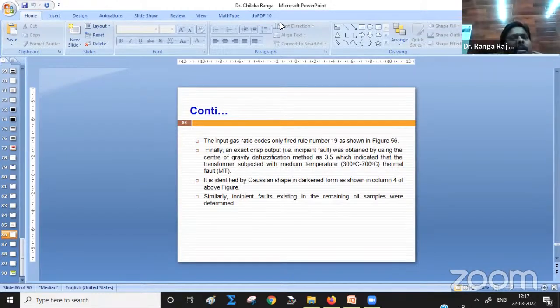DGA methods generally detect all incipient faults - I just discussed that. So all the conventional fault methods, the IEC ratio code method, Duval triangle method, Doernenburg method - if you see the literature, you find some basic methods through which one can determine the fault present inside the transformer, the incipient fault. Outside-transformer faults we know: line-to-line, line-to-ground, three-phase faults, short circuit faults - we know them, and they affect the life of the insulation, isn't it?